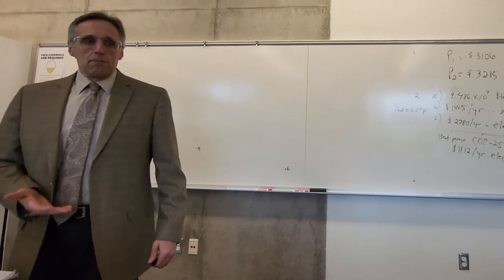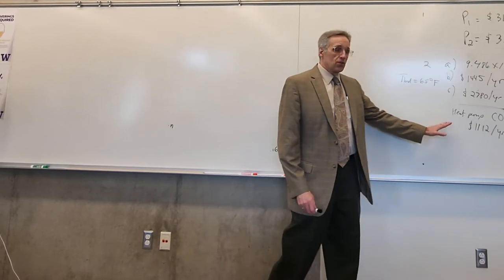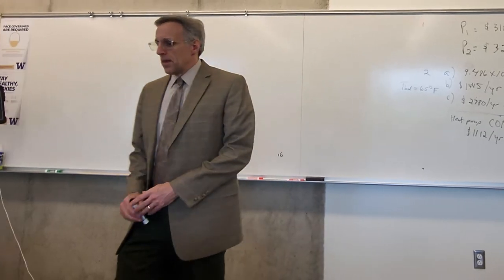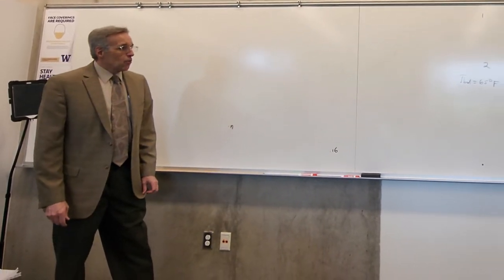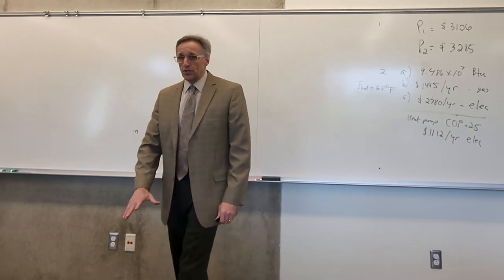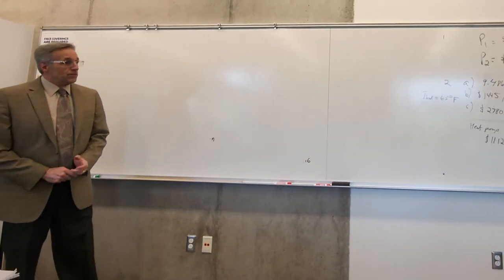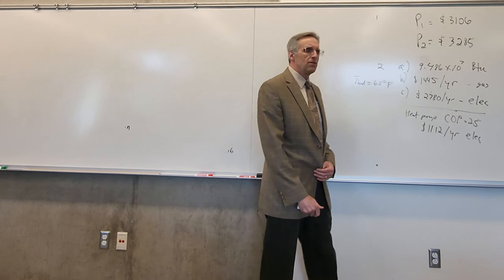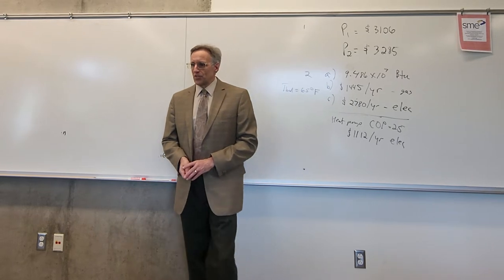Although now, the Japanese have come out with heat pumps that claim to be efficient all the way down to like minus 15, minus 20 Fahrenheit. So we are seeing better air source heat pumps. But for cold climates, a water source heat pump would be a better bet. With a ground source heat pump, the ground stays at a constant temperature, even though the air is going to be up and down. The ground is generally 45 to 50 degrees year-round, 45 to 55 most places. And that's going to give you a more consistent performance, a more consistent cost.